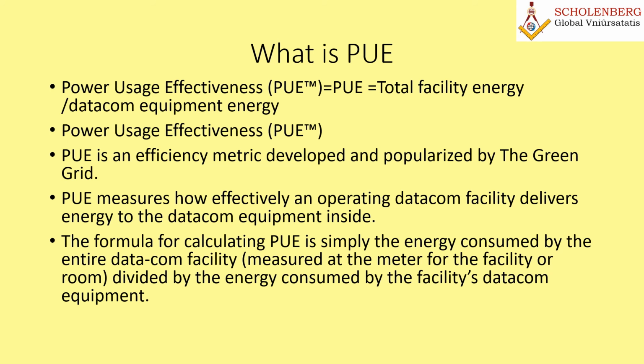It is also important to understand that an enterprise can take steps to reduce total energy consumption yet achieve a worse PUE. Extensive consolidation and virtualization, or purchasing Energy Star rated servers, could significantly lower the datacom equipment energy number in the denominator of the PUE equation. So it should be recognized that the PUE metric is impractical to use as a means of quantifying projected energy efficiency at the design stage of a datacom facility.